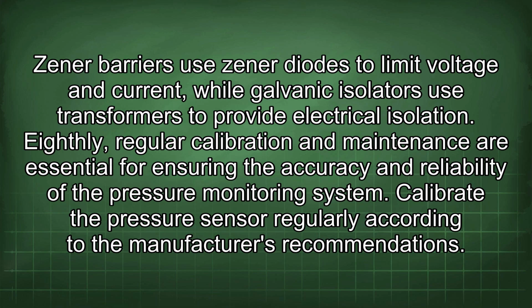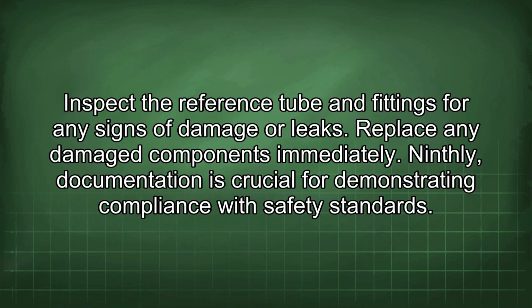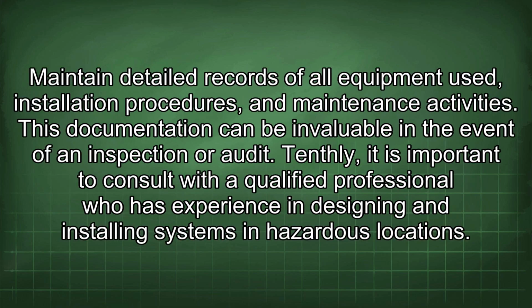Eighthly, regular calibration and maintenance are essential for ensuring the accuracy and reliability of the pressure monitoring system. Calibrate the pressure sensor regularly according to the manufacturer's recommendations. Inspect the reference tube and fittings for any signs of damage or leaks. Replace any damaged components immediately. Ninthly, documentation is crucial for demonstrating compliance with safety standards. Maintain detailed records of all equipment used, installation procedures, and maintenance activities. This documentation can be invaluable in the event of an inspection or audit.